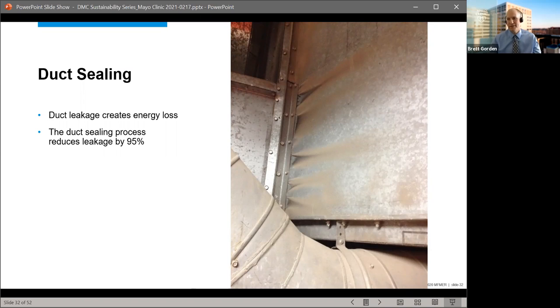Another interesting one, at least I find interesting as a mechanical engineer, is duct sealing. This has been a great strategy for us. It's basically things you don't see in a building, but any building with older ductwork wouldn't be sealed to today's standards. So it's a huge energy loss, especially in commercial buildings where you're moving a lot of conditioned air, because if you're losing it along the way, you have to create more to keep the building temperature comfortable for occupants.